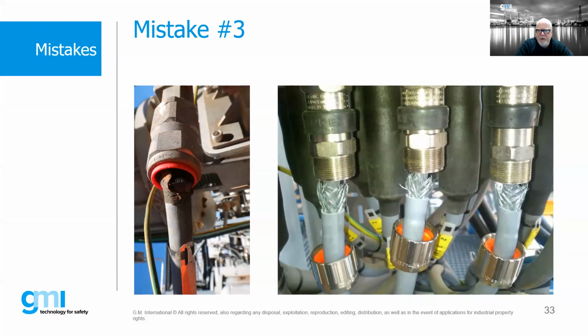That brings up another point. What you see on that picture on the right-hand side, you see some cable glands, and then behind there, those are actually cable shrouds. I strongly recommend against the use of cable shrouds because, number one, in many cases, they just hold the moisture inside against the gland. They cause a lot of problems. But secondly, if we're doing an inspection, we have to slide those shrouds down or cut them off. And at that point, then, okay, we've removed them. So I know many customers are getting away from the use of shrouds. I would highly recommend you don't use them as long as you're using a high quality gland that maintains a very good high IP rating. So that's my own 2 cents.